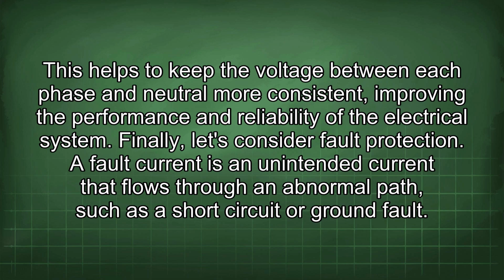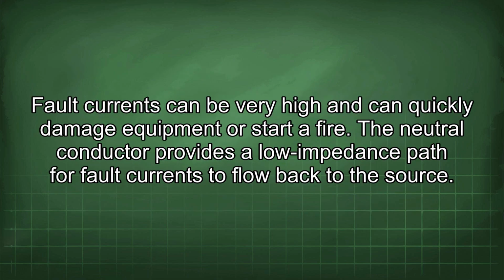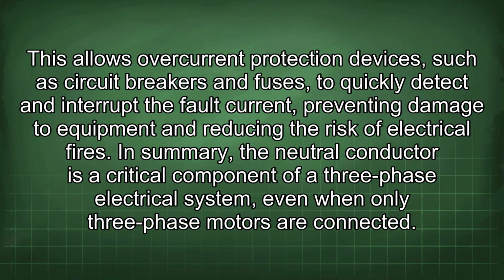A fault current is an unintended current that flows through an abnormal path, such as a short circuit or ground fault. Fault currents can be very high and can quickly damage equipment or start a fire. The neutral conductor provides a low impedance path for fault currents to flow back to the source. This allows overcurrent protection devices, such as circuit breakers and fuses, to quickly detect and interrupt the fault current, preventing damage to equipment and reducing the risk of electrical fires.